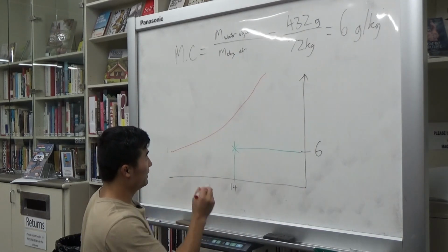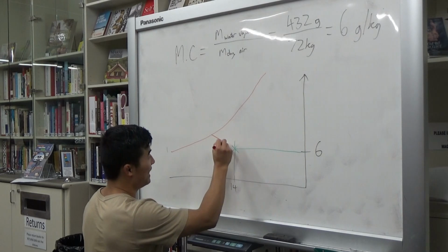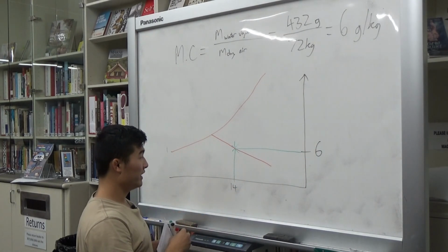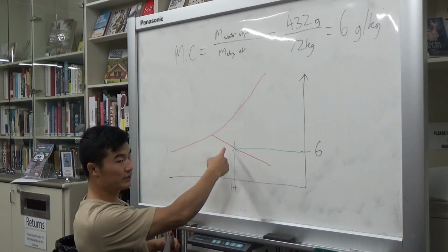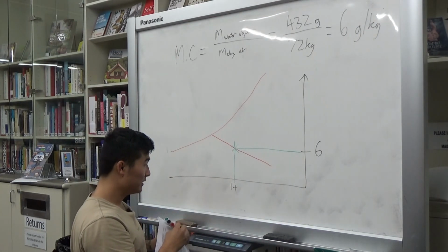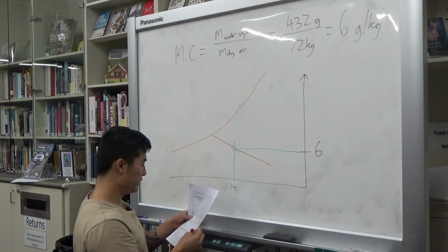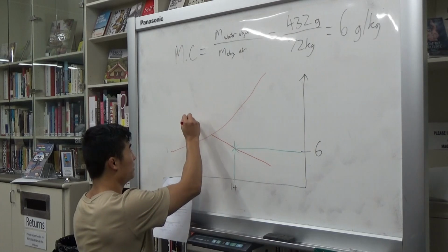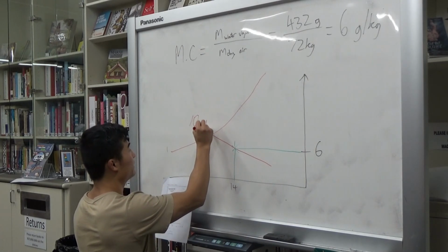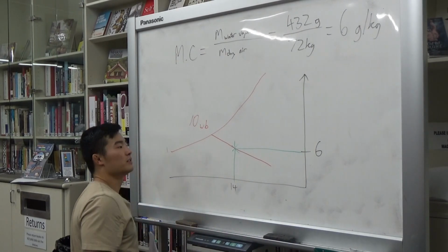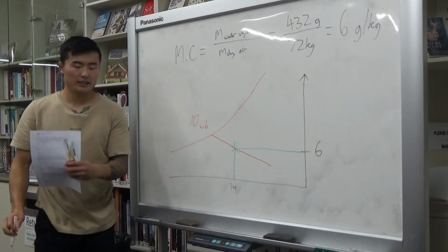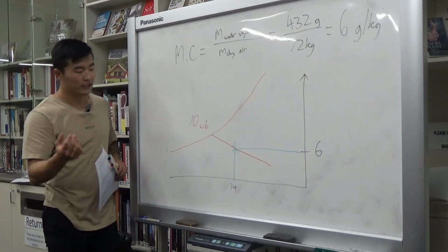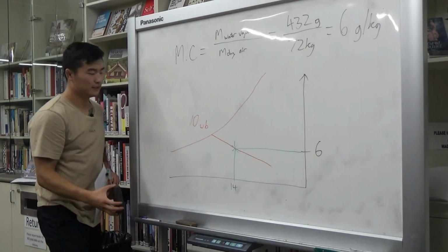And you're going to find the diagonal, because wet bulb runs diagonally. So you're going to find the diagonal line that intersects with this point of intersection. And you will find that that line will be 10 degrees wet bulb. Okay, so this is a little bit harder because there's another step involved, figuring out what the moisture content is.